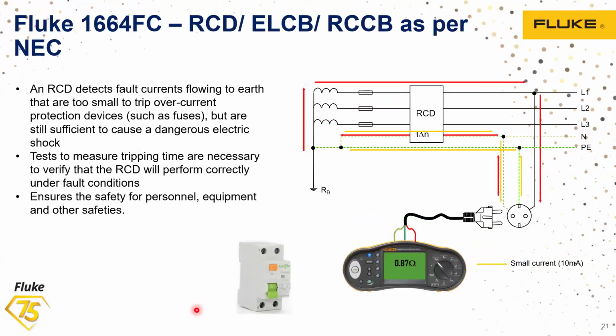And the next recommended test is the RCD testing. We have to know that the RCD is for personal safety as well as equipment safety. Now, over a period of time, what happens? When you look at the RCD, there will be a test button here. Once you press this button, automatically it will trip. Once it trips, if it is live, it will cut off the power.